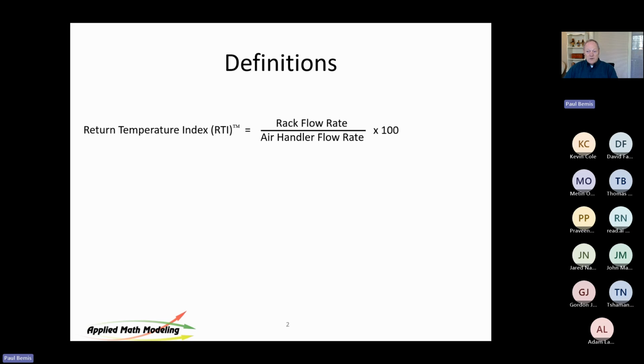And at atmospheric level, that turns into, for today's servers, about 125 CFM per kW. And I'm afraid for my international customers, I'm going to use American units today. So I'm going to use CFM. So about 125 CFM per kW is going to be in the numerator. Denominator is how much air are you throwing at the problem to take care of the numerator. You want that denominator to always be bigger than that numerator, or else you're going to have, particularly in a contained case, pressure differential, the incorrect pressure differential.